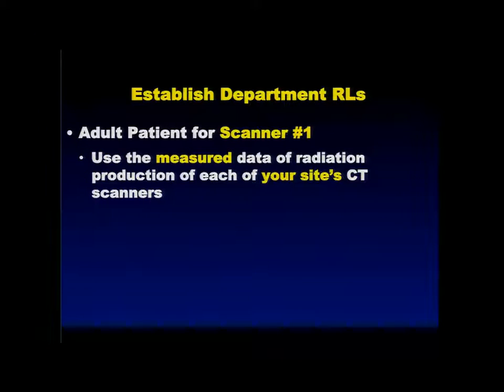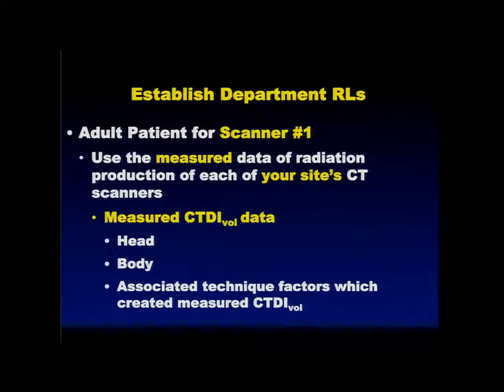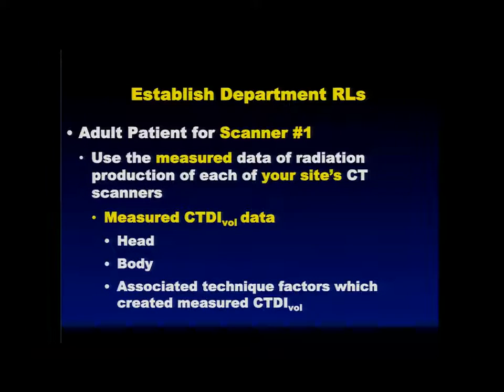The other important thing is the CTDI vol measurements tell you how the scanners differ from one another with respect to dose. We've accounted for both the uniqueness of the radiologists and the uniqueness of each scanner by starting with the adult. This is a radical concept — we're now going to actually use the data the qualified medical physicist measures every year to have an impact on patient care, rather than just putting it in the file and dragging it out every time an inspector comes.